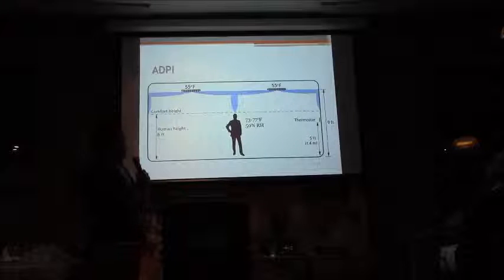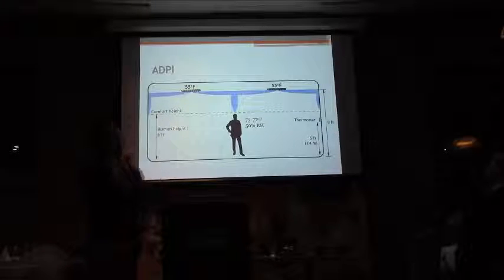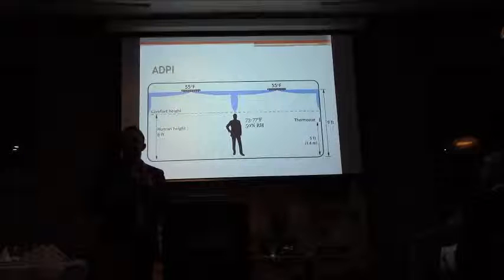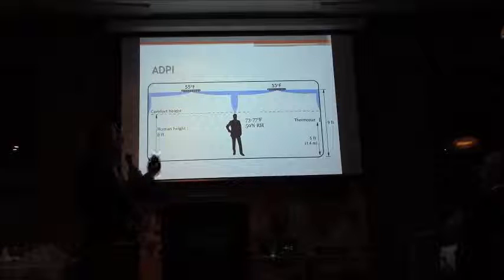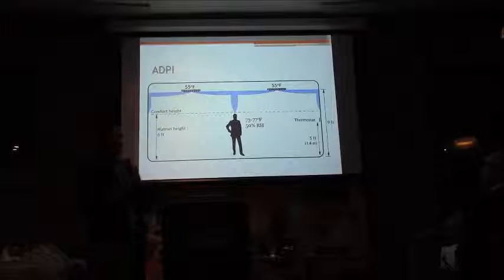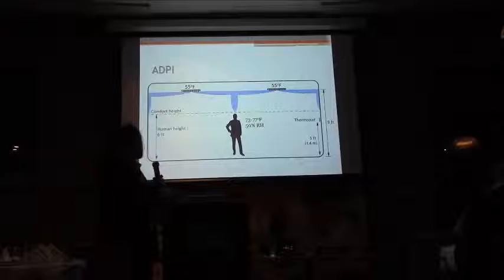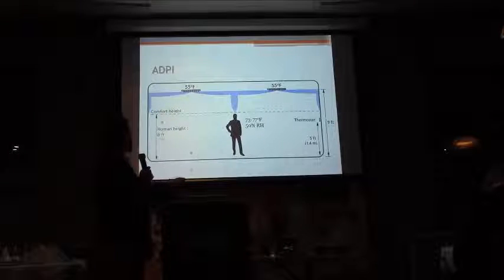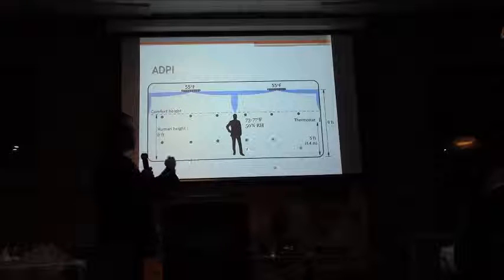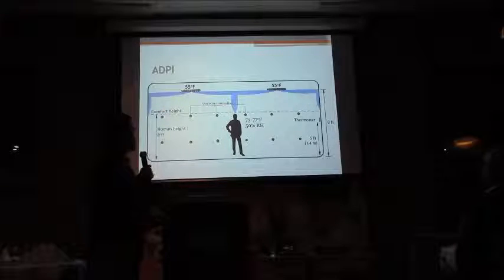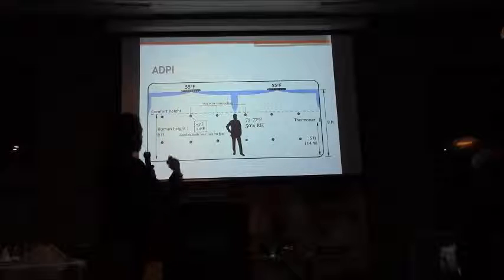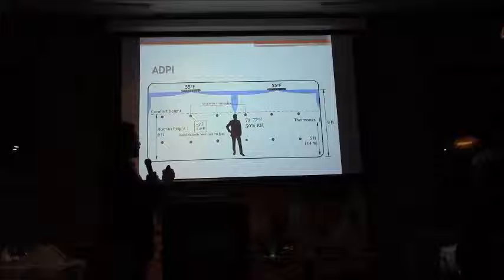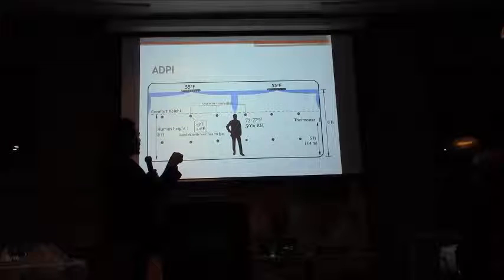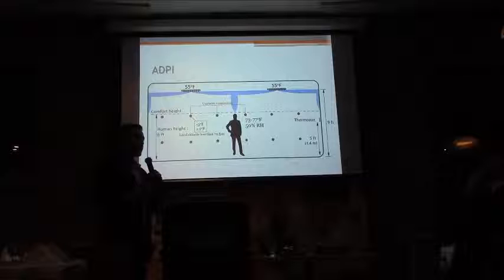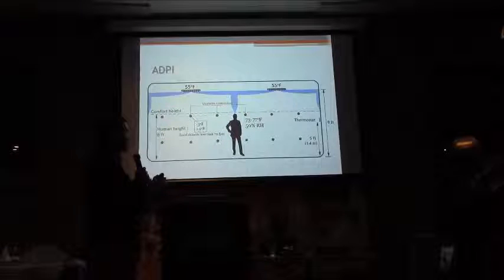So the effective draft temperature brings me to the next slide. It's ADPI. It's the Air Diffuser Performance Index. This is how you rate the effectiveness of your ventilation system. The higher your ADPI, the more efficient the ventilation system that you have. So basically what ADPI is, is a bunch of effective draft temperature readings evenly distributed across the room. So let's say all those red dots there are where I measured my effective draft temperature. And to have a pass, you want to have an effective draft temperature of between -3 and +2. If you're outside these bounds, it's a fail.